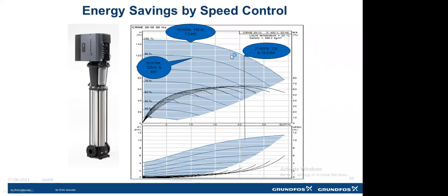So what happens if we reduce the speed is that the pump curve also shifts to the lower side. Here we can see the pump curves at variable speed: 100%, 90%, 80%. Also, the efficiency curves change as per the pump speed. A common thumb rule: we explained about installing two or more pumps if the requirement is variable, changing over a period of time. Through VFD also we can save energy, but for a variation from 50% to 100% of the flow capacity.